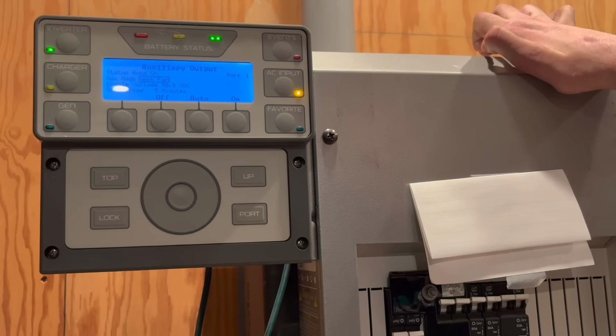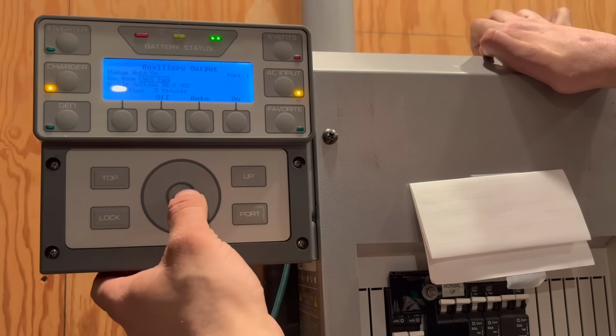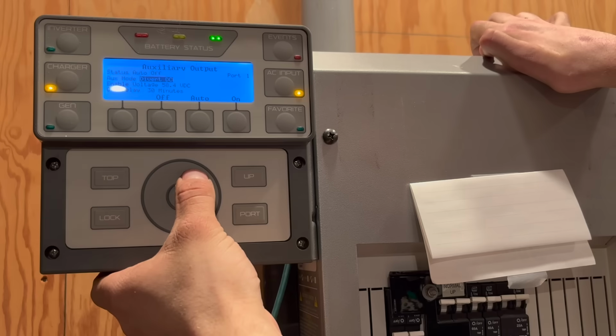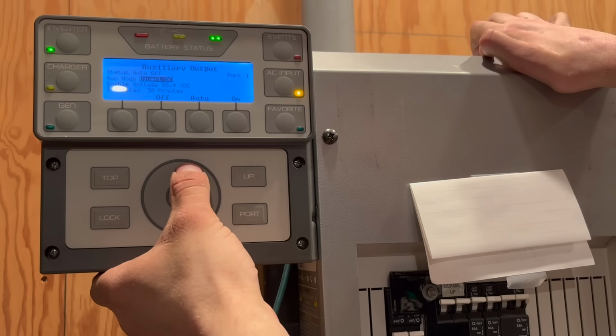The Outback Mate 3S provides configuration and monitoring capabilities for the system and also allows for auto generator start through a relay when the batteries reach about 52 volts.